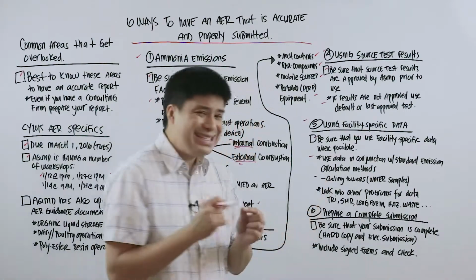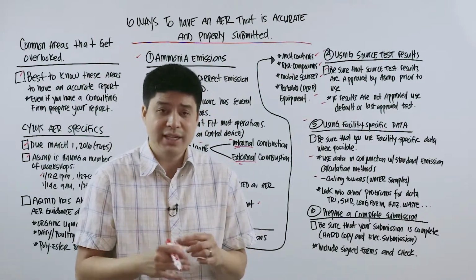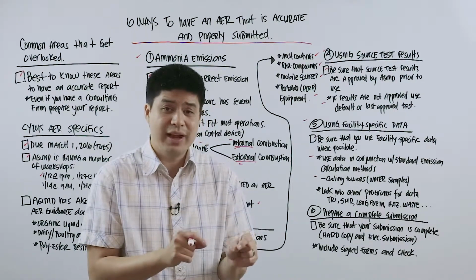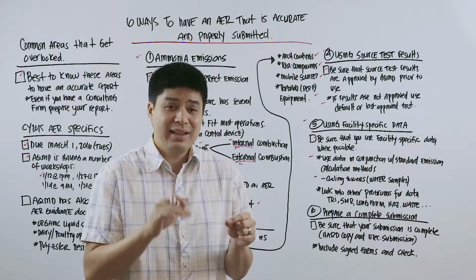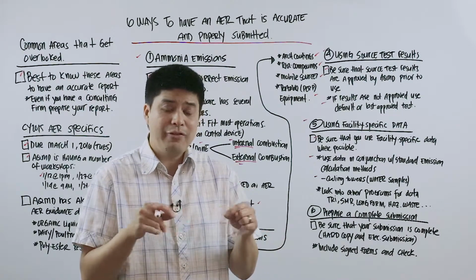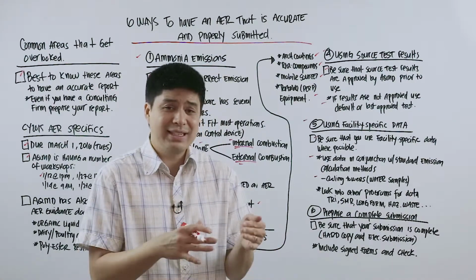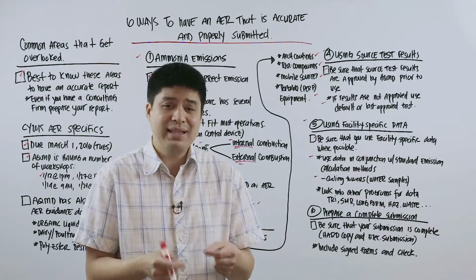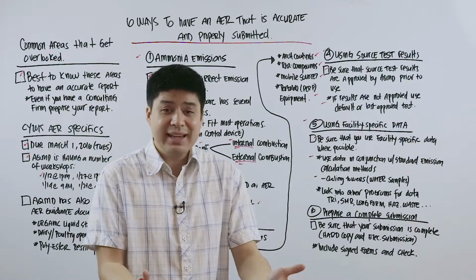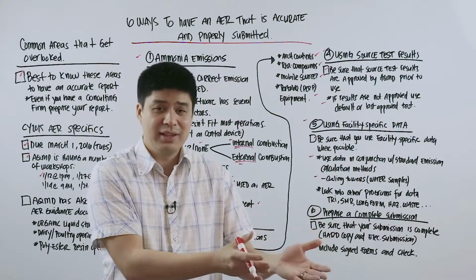One example of where we see this to be a benefit is when reporting emissions from cooling towers. Interestingly, reporting emissions from cooling towers using the default emission factors will produce emissions that grossly overestimate the process. We'll link up a few studies that have noted this and have tried to derive corrections for this overestimate, but the best thing that you can do if you have a cooling tower is simply collect the data needed to use the facility-specific data within the standard emission calculation formulas.